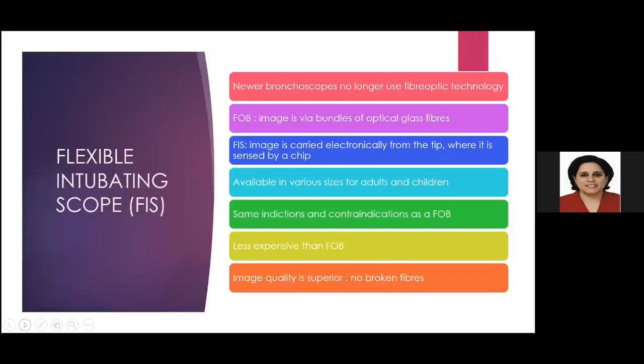Now we come to bronchoscopes. There is a newer bronchoscope called the flexible intubating scope, which no longer uses the technology of a fiber optic bronchoscope. In a fiber optic bronchoscope, the image used to be conducted via bundles of optical glass fibers. In this, there are no optical glass fibers. The image is carried electronically from the tip, where it is sensed by a chip, which has a light source as well as a small camera, and the image is transmitted to a proximal camera.